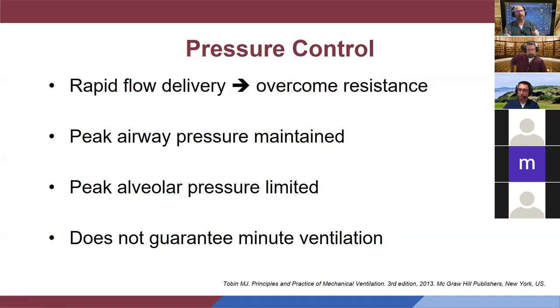It's basically on demand. If you want to take a big deep breath, the machine's going to give you the flow. If you want to settle down and relax and calm down, then the flow is going to decrease based off your demand. But it has that demand. So back to the scenario with Darren, if he starts waking up, taking these big giant breaths, the machine will start escalating the pressure and support him with the flow, and then his work of breathing will come down. So it's the complete opposite of the dual control. So you get that rapid flow on demand. Also, you're able to maintain your airway pressures.